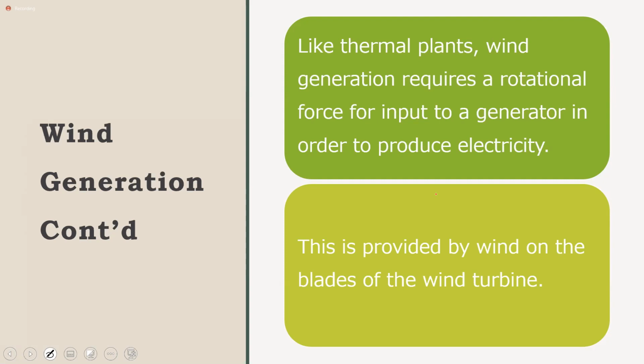But you have variable wind speed generators, using turbines that use synchronous machines or induction machines. If it's induction, then where is the VAR support coming from? Because it will require VARs to operate that induction generator. So these are considerations that will have to be made when we're talking about integration.